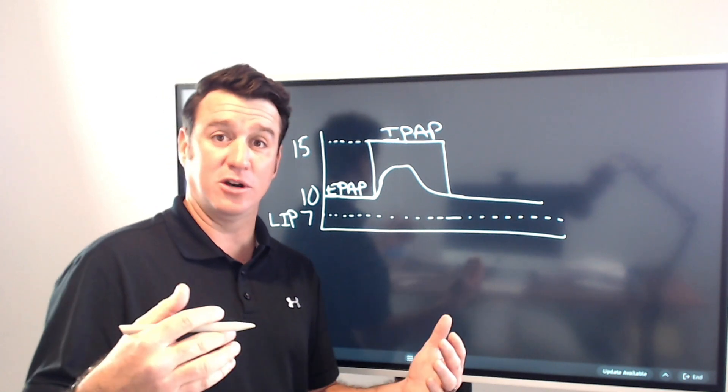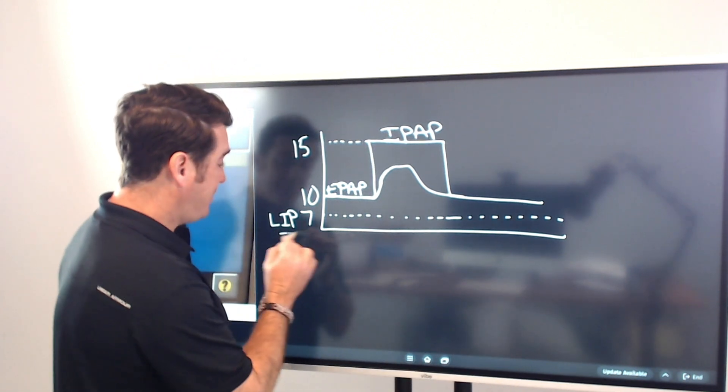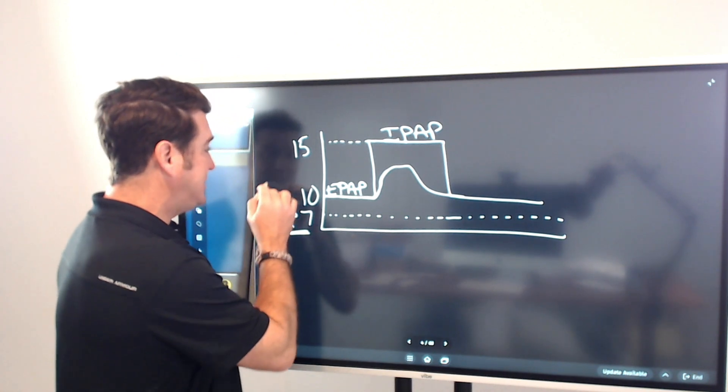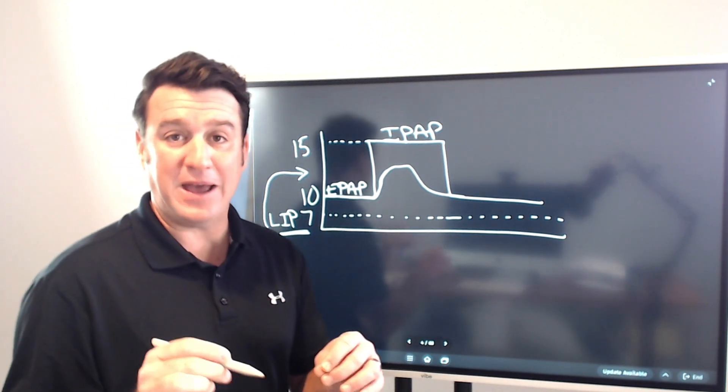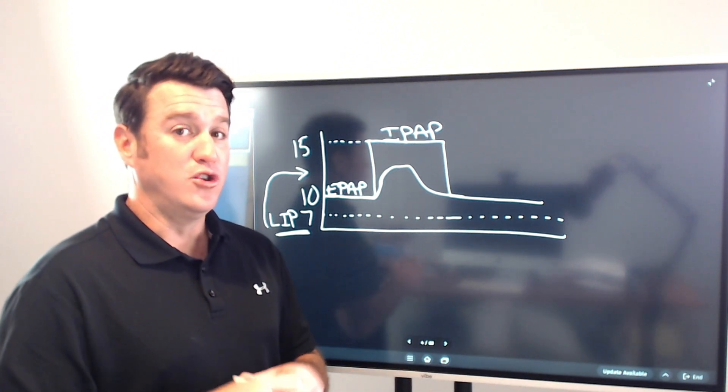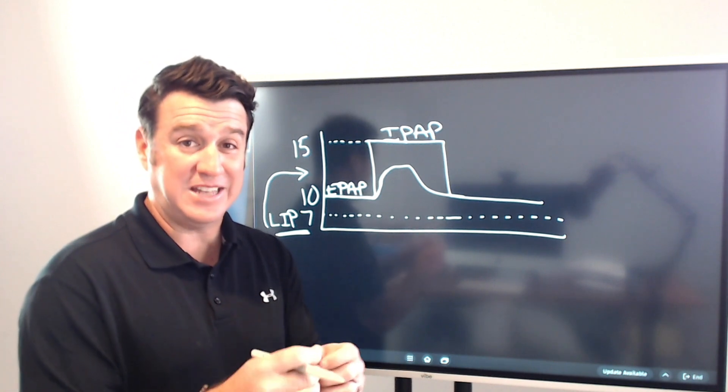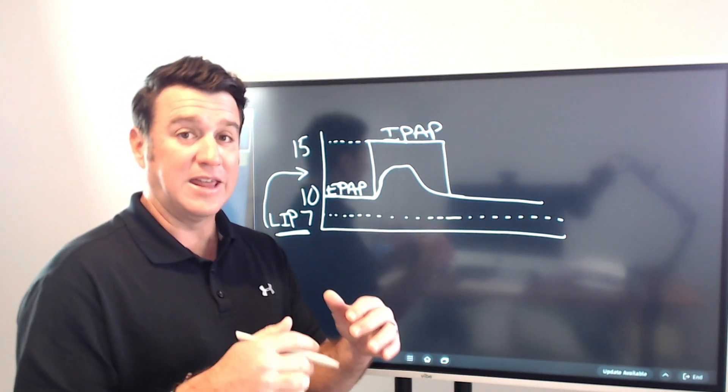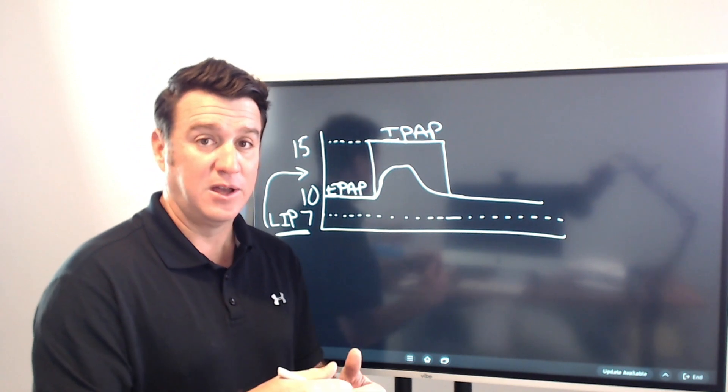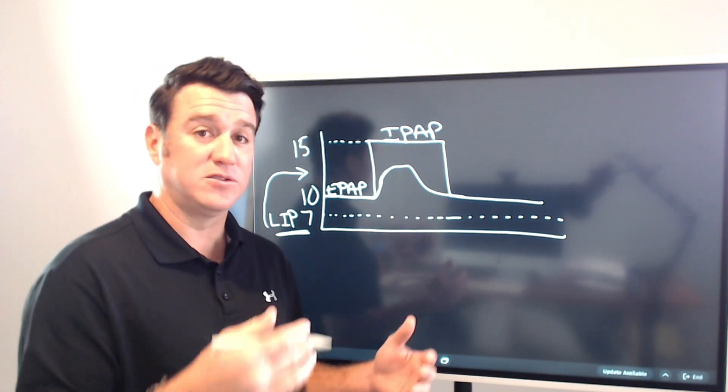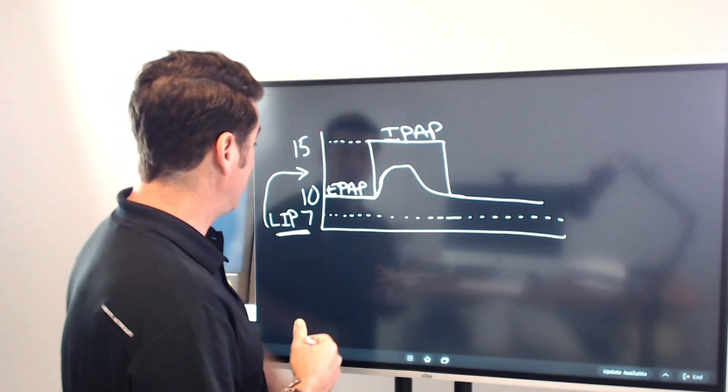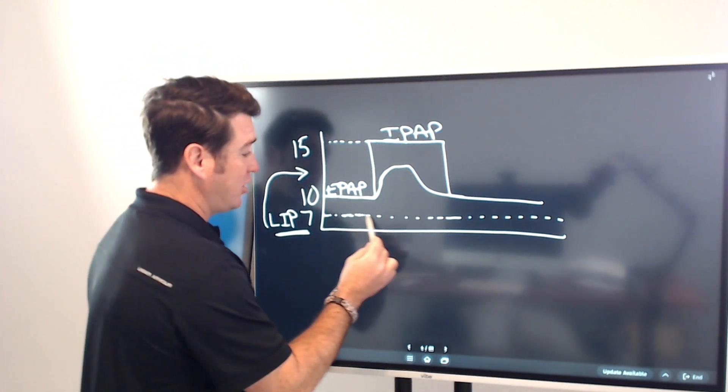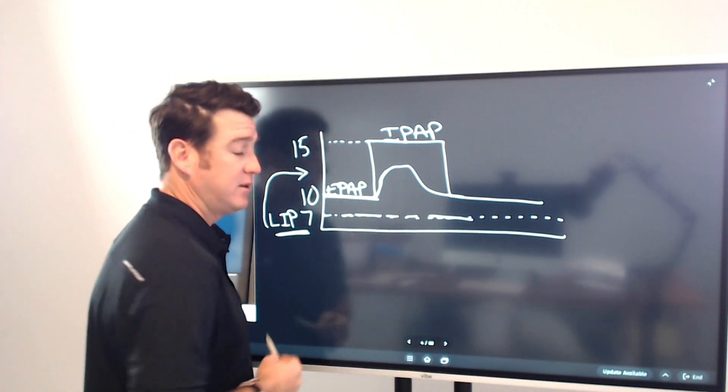How do we set it appropriately? The LIP should always be set between EPAP and IPAP. You want that lower inspiratory pressure alarm to be set at a threshold that will notify you if the inspiratory pressure fails to reach whatever the threshold is you have this alarm set at. This alarm is never going off because we're already above it.